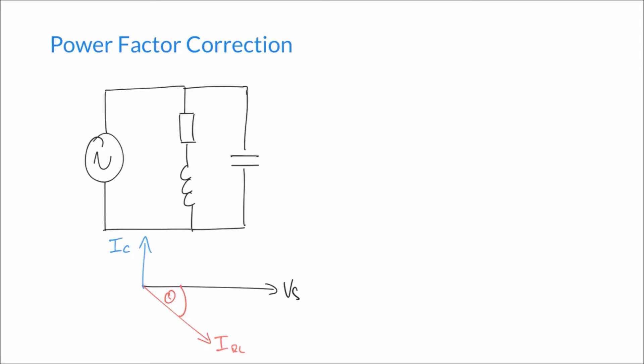By selecting an appropriately sized capacitor, we can produce a capacitor current that is going to cancel out the reactive component — the vertical component — of our motor current, or the current going through the resistor and inductor. If our capacitor current is sized such that it balances or cancels out our reactive current, we're left with a resultant current that is completely in phase. Our resultant current would be in phase with the supply voltage, because we've used that leading capacitor current to cancel out the lagging effect of the inductor.